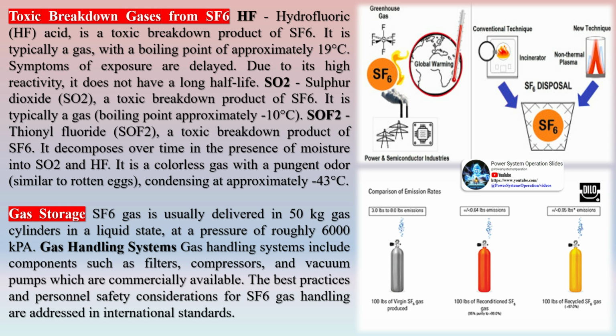It is typically a gas, with a boiling point of approximately 19 degrees Celsius. Symptoms of exposure are delayed. Due to its high reactivity, it does not have a long half-life. Sulfur dioxide, SO2, a toxic breakdown product of SF6. It is typically a gas, boiling point approximately -10 degrees Celsius. Thionyl fluoride, SOF2, a toxic breakdown product of SF6. It decomposes over time in the presence of moisture into SO2 and HF. It is a colorless gas with a pungent odor similar to rotten eggs, condensing at approximately -43 degrees Celsius.